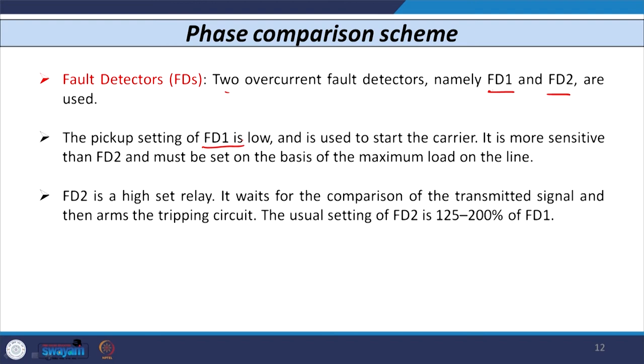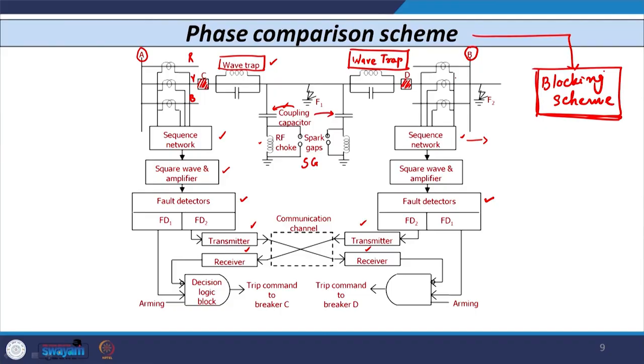The setting of FD1 is lower than FD2 — FD1 is set based on the full load current of the line and is more sensitive. FD2's setting is 125 to 200 percent of FD1, and there is a timer connected with FD2. FD1 operates immediately as soon as the current exceeds full load current, whereas FD2 operates only once the timer period is completed.